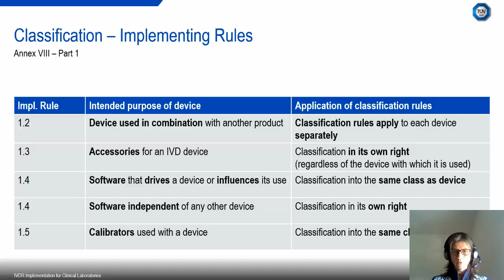So we have 10 implementing rules. Here you can see the first 5 of them. In the next slide we see implementing rules 6 to 10, so the second set of implementing rules. These rules give guidance for classification of control materials with assigned value, which should be in the same class as the device they are meant to verify the performance for. If multiple classification rules apply, the classification resulting in the higher class is the one that determines the classification of the device.